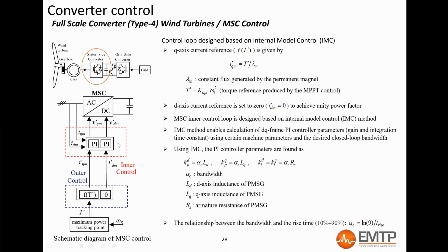A two-level control loop is used for the Q-axis. The reference of this loop is the machine electromagnetic torque. This reference is provided by the maximum power point tracking, or MPPT, and is set to get the maximum power out of the wind. It uses the blade rotation speed and some optimization curves to find the optimal electromagnetic torque available. This device will be discussed in detail in another video. The torque is transformed into a Q-axis current reference using the permanent magnet constant flux and a coefficient which depends on the blade aerodynamic, which is hard-coded in the version available in EMTP 4.1, and which has been determined in collaboration with wind turbine manufacturers. More information will be provided in another video.